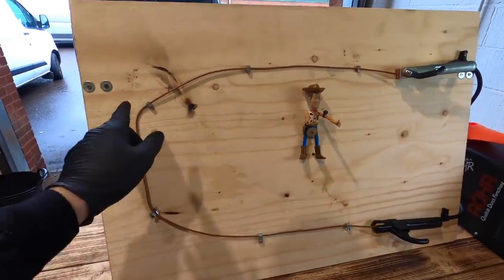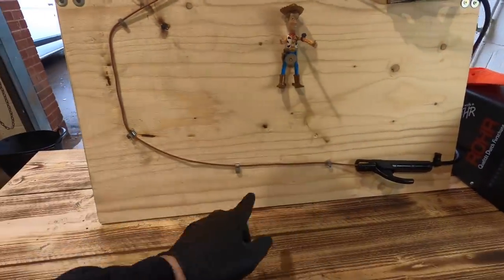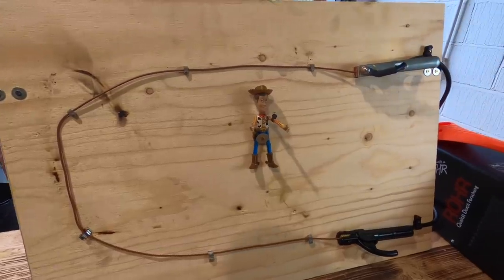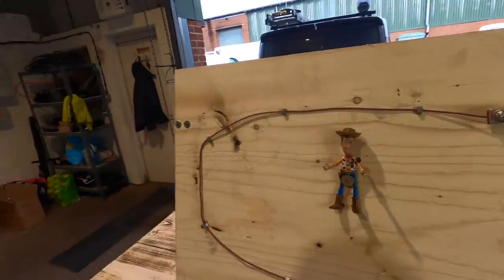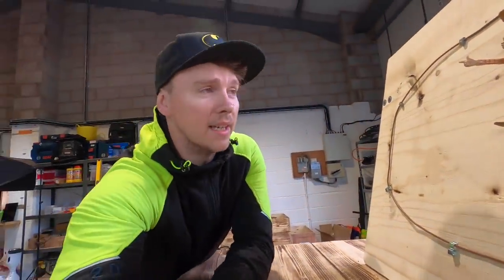We don't really stock any plastic stuff anymore. I've set a rig up — you've already seen it from the last video — because the cable dropped even with plastic clips fitted the correct way, so the nail was below to support the weight. What we have set up here is three plastic normal twin clips and three metal twin clips. Woody is our rescuer — maybe our firefighter — because a lot of stories I've heard in the past...